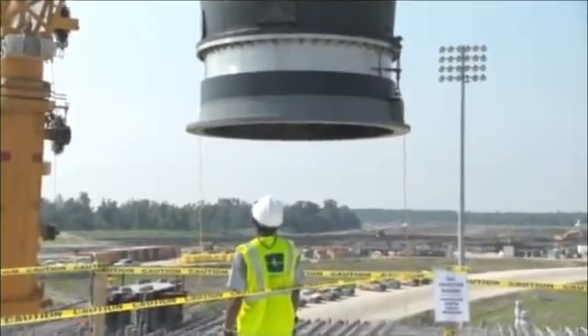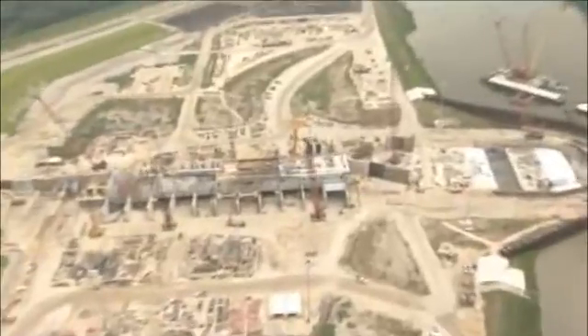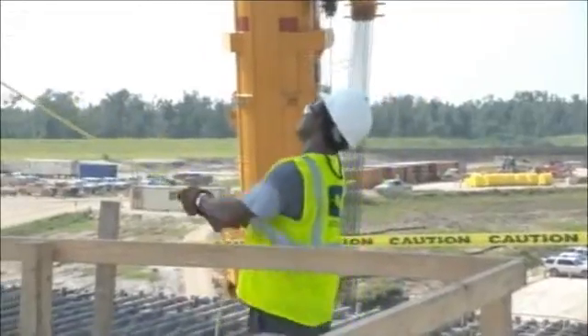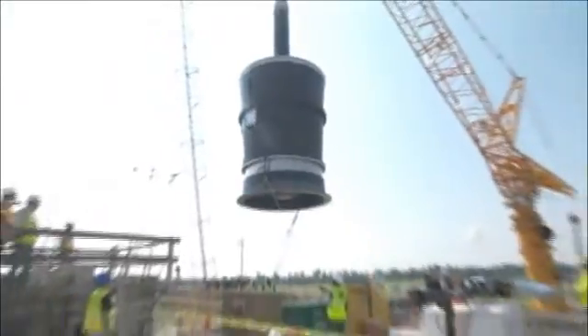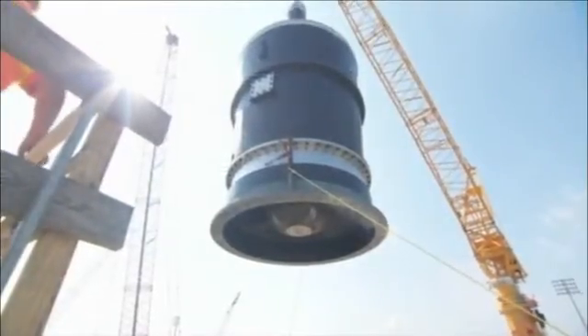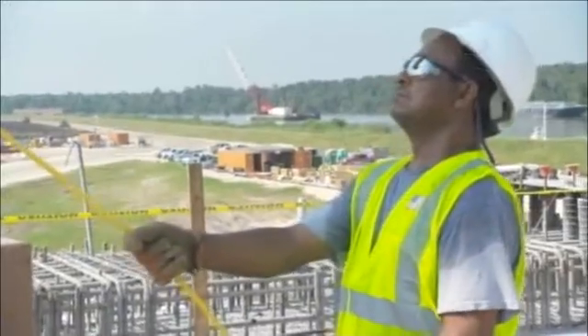It's rated at 800,000 gallons per minute. Because of the importance of this project, every component went through a QA process. The first pump had 630 pages of quality documentation required to show that our pump met the specification requirements. It's mainly about nailing the hydraulics. The pumps are way too large to physically test other than in the field when installed, so you base it on a model using affinity laws.